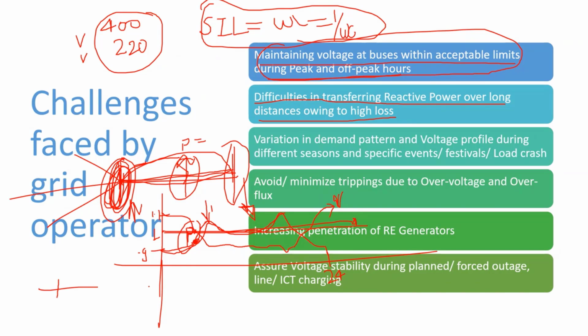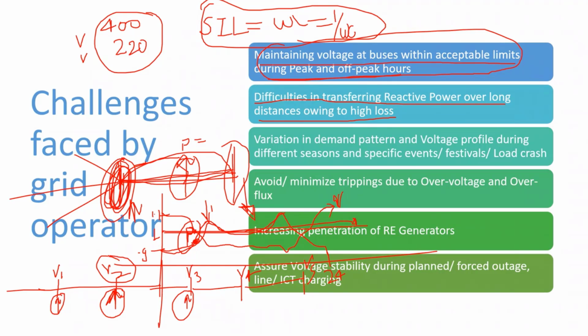For maintaining the reactive power, let us say 5 nodes are there in the system. Here V1 is there, this is the V2 substation, this is V3, V4 and V5. If you have to maintain the voltage of this node, let us say V2, you provide most of the reactive power support over here. You may provide some reactive power support from this point and some from this point, a very small amount. But you don't want to control the reactive power from, let us say, this V6, which is located quite far away.